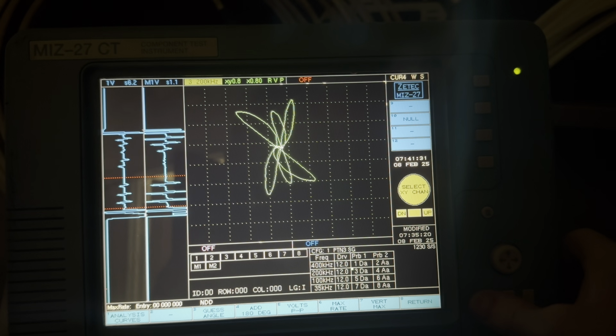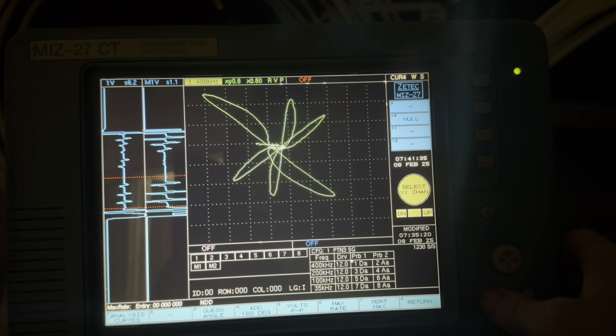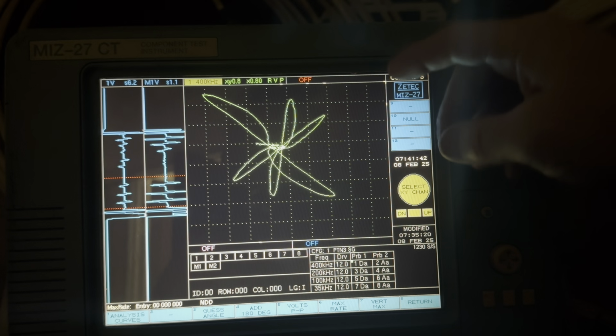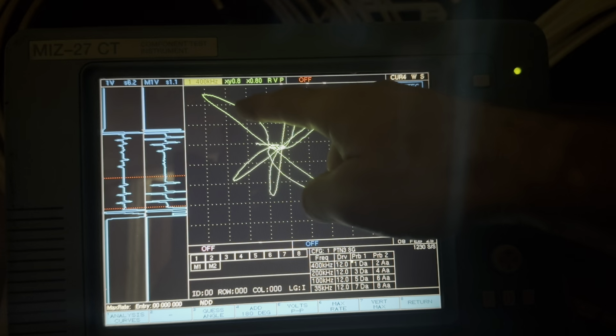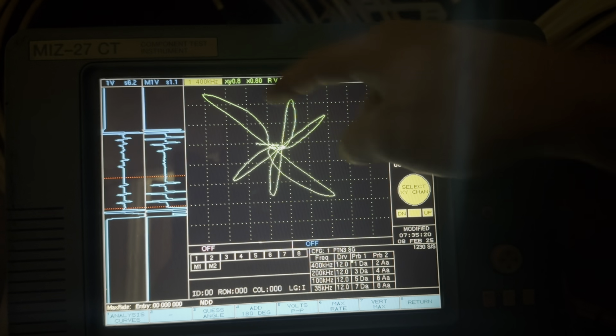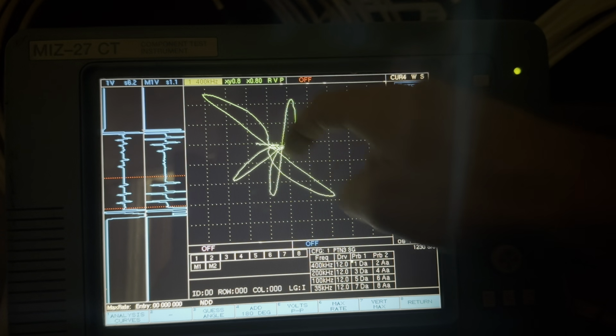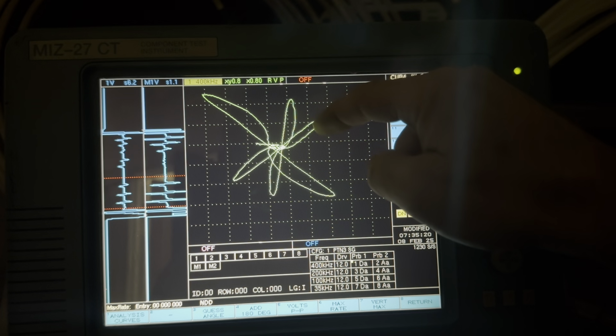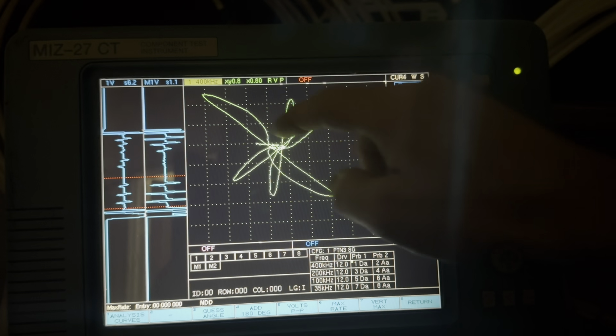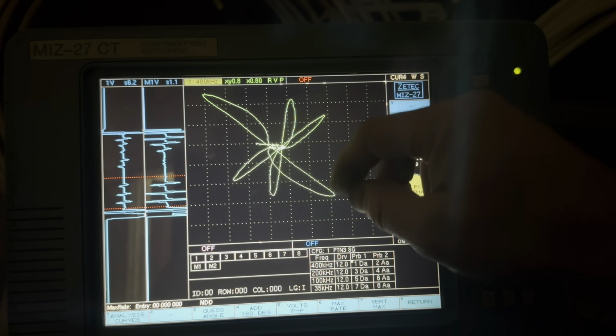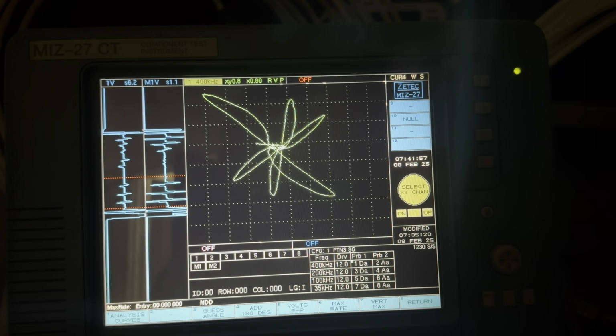So to have a more accurate sizing curve, you've got to use a frequency like this. And this meets that ASME code requirement of having substantial phase difference between your 100% hole and your 20%ers. In this particular case, it looks like there's about 90 degrees between the 100 and the 20s, not to be confused with the 90 degree spread between shallow IDs and shallow ODs, which the F90 frequency will give you. Now, what does this look like on our analysis curves?